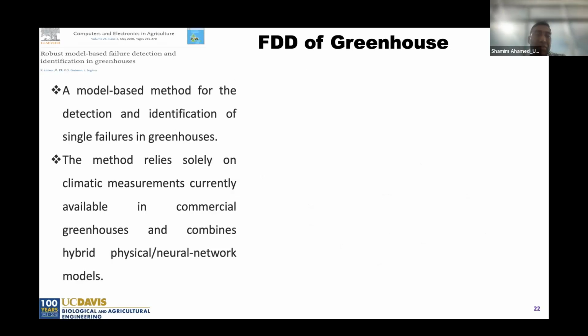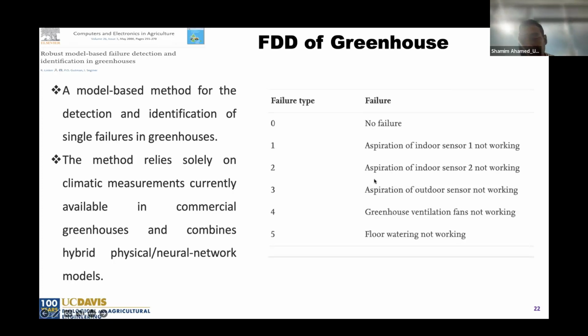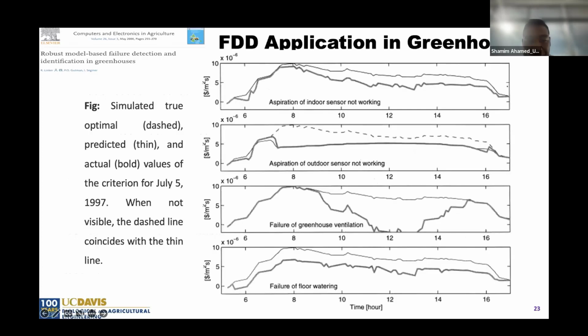The second research, also done around 2000, mostly used a white box, knowledge-based model to develop fault detection and diagnosis in greenhouse applications. They tried to identify faults in the indoor temperature sensor, the relative humidity sensor, the outdoor sensor, and also the ventilation fan, whether it's working or not, and the floor watering, especially for hydroponics, whether the hydroponic pump control system has any problem.